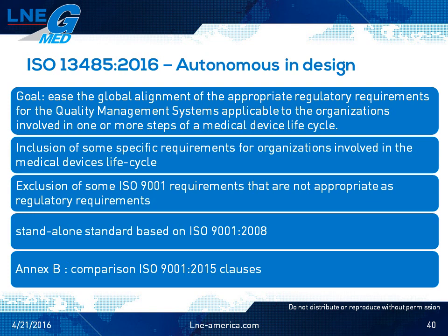So first, why doesn't the new ISO 13485 standard follow the HLS structure? First, for timing reasons. The review process of ISO 13485 started before the HLS structure was mandatory. The next revision, however, will be consistent with the HLS structure. Also, among the provisions of ISO 9001:2015, there are points that are not in accordance with the spirit and text already in 2003 of ISO 13485, such as customer satisfaction, the documentary simplification, and the principle of continuous improvement of the efficiency of the system.